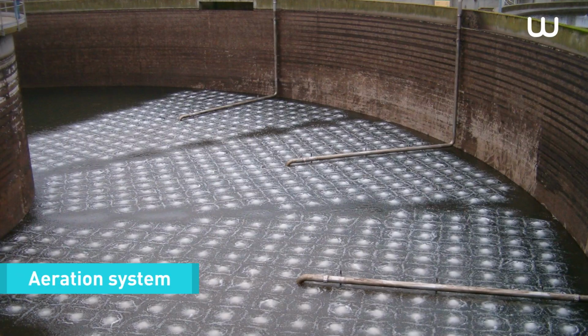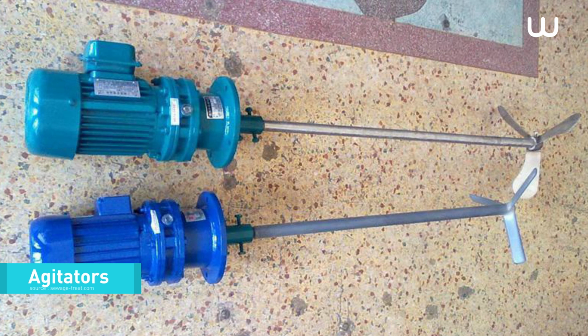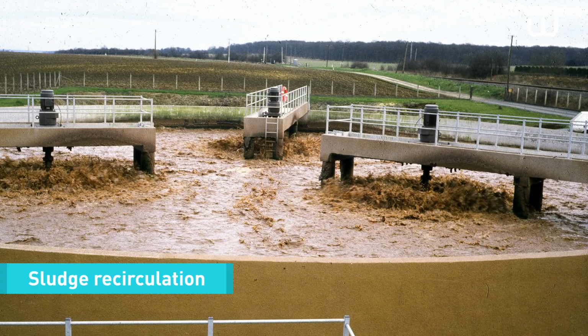The aeration system provides oxygen for the microorganisms as well as stirring during the biological treatment process. Two types exist: surface aerators and air-blowing systems. Agitators homogenize the effluent in the tanks and prevent deposits. A system with several pumps for extraction and sludge recirculation purposes.